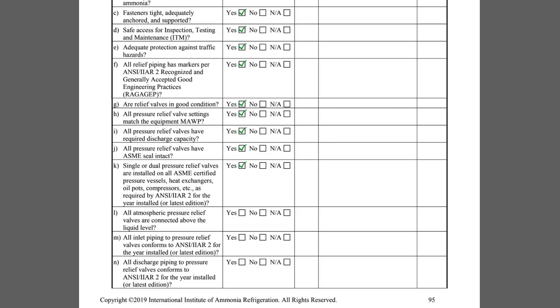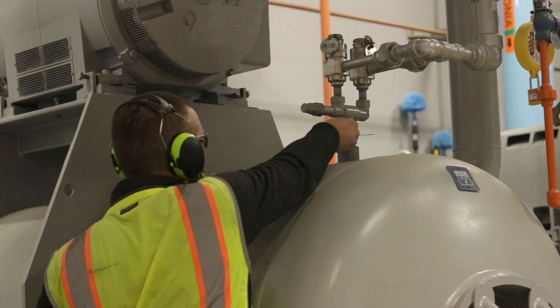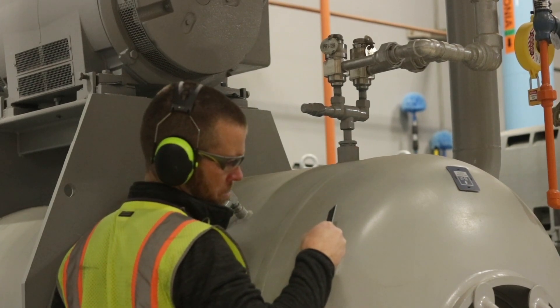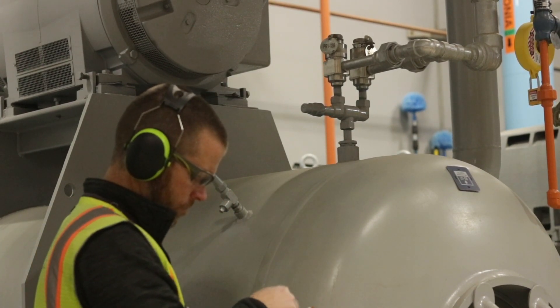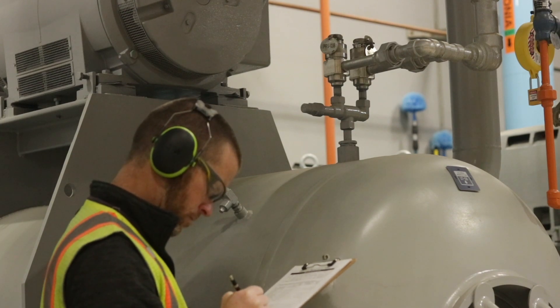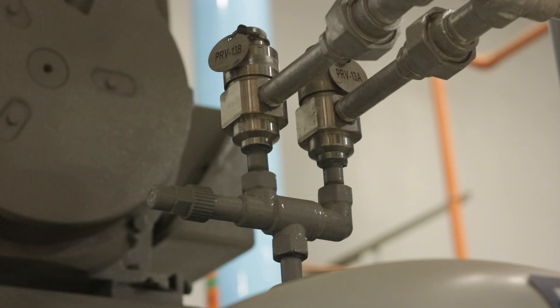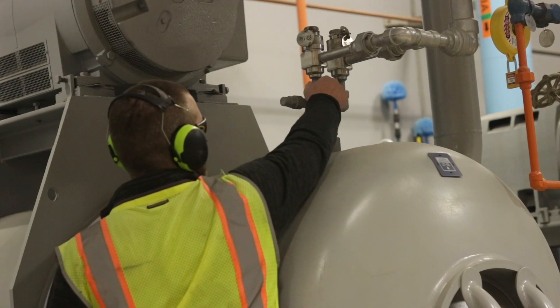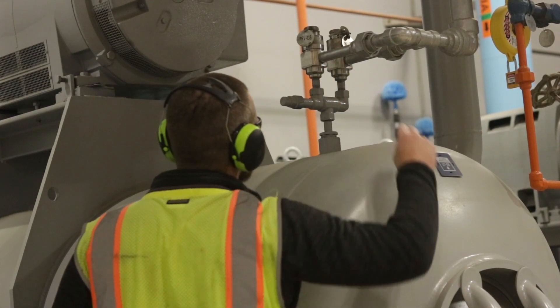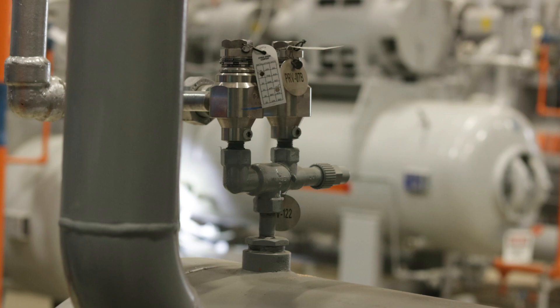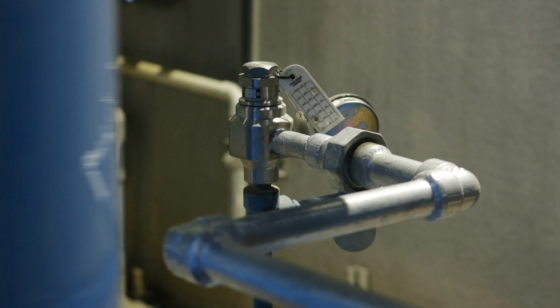Item K inquires if the proper relief valve assembly is installed per IIAR Standard 2. Standard 2 requires that pressure vessels with an internal volume greater than 10 cubic feet be configured with a dual relief valve assembly, consisting of a three-way relief isolation valve connected to two relief valves. In this arrangement, only one relief valve is active at any time, which allows the other to be replaced while the equipment is still under pressure. Vessels with an internal volume less than 10 cubic feet can have a single relief valve.